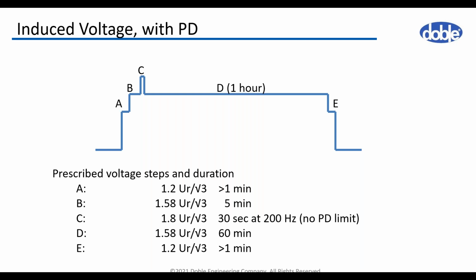After that, it's increased to 1.2 rated voltage for a short period in order to obtain a stable reading of the picocoulombs, and then increased to 1.58 multiplied by the rated voltage for 5 minutes, where we also obtain the partial discharge level. After that, we go to the stress level, 1.8 rated voltage, and the duration of the stress level depends on the test sequence. No limit in terms of partial discharge is defined for this level.